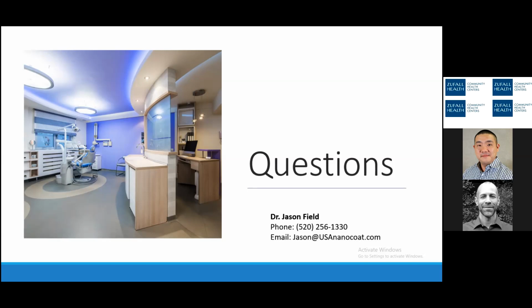All right, next question. What maintenance is required for PCO reactors? So there is very little maintenance. There are no filters. The only thing that's required is every 30 months, you're supposed to replace the reaction chamber. So it kind of unscrews like a light bulb, and then there's 2 little screws that hold the reaction chamber in place. And that's the only maintenance.